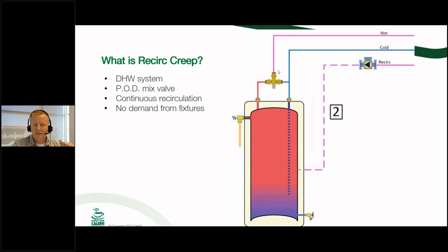Now, if you did not have a mixing valve, that tapping would be perfectly fine. And you might even see in some scenarios where you're tapping into the bottom of the tank, and it's the same scenario. If you're doing either mid-tank tapping or at the bottom of the tank tapping, if there was no mixing valve, everything would be just fine. But in many cases, mixing valves are a requirement per code for commercial buildings and things like that. So you have to have them. So the issue here is if you've got that mid-tank tapping or at the bottom tapping at the cold inlet or at the drain, now all of a sudden, instead of 115 degrees coming right back to the cold inlet up here, that 115 degree water has to come into the bottom or to the midpoint there of the tank. Now it either has to travel backwards up through the dip tube or through the hot inlet or the hot outlet of the tank to the hot inlet of the mixing valve.